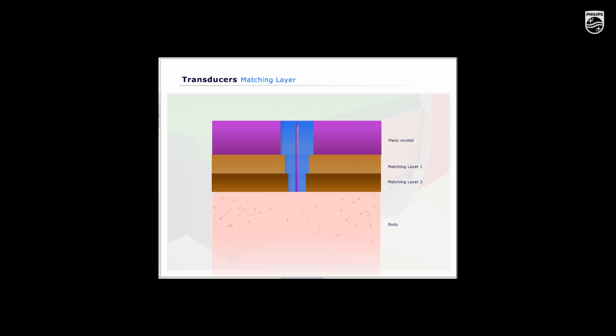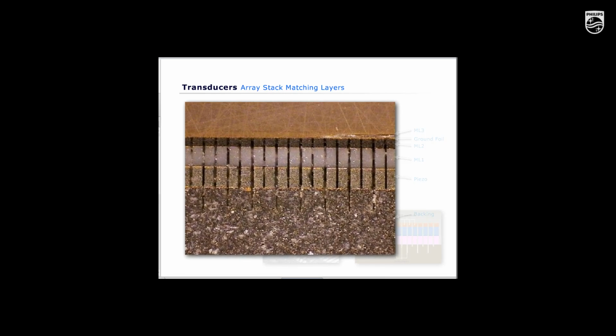The impedance of each matching layer is of intermediate values to compensate the impedance of the elements. Typically, 2 layers are used, but 1 or 3 is also possible. Next to the matching layers, the lens also acts as a matching layer. This is a real picture of the layers inside the transducer. You can see the backing material, the piezo element, the 3 matching layers, and a ground foil.